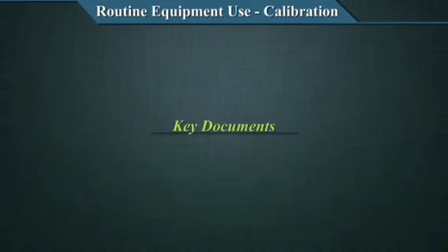And one more set of documents that are required. So we talked about different kinds of documentation: the product insert or the data sheets from calibrators, the calibration certificates, the calibration matrix, and one more set of documents that come out of calibrations that is very important, especially in the case of analytical equipment, is your raw data.